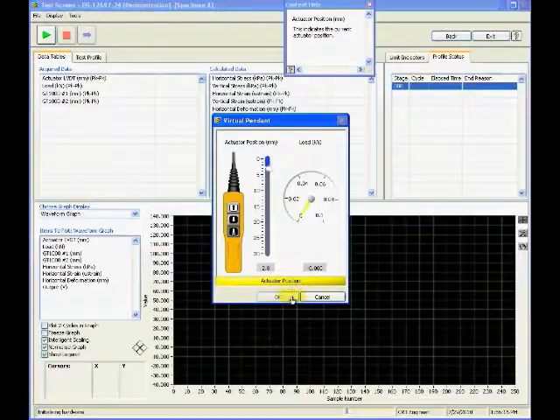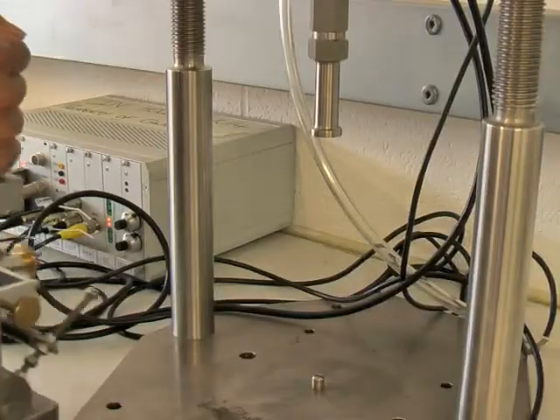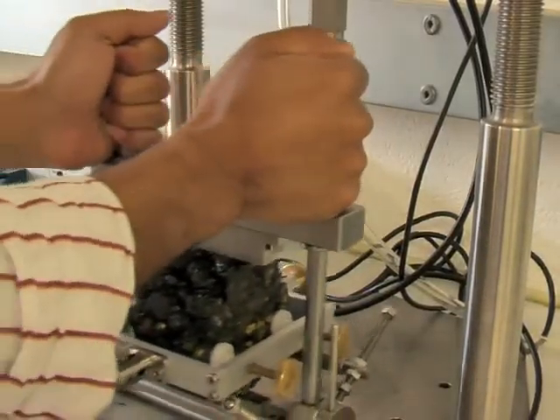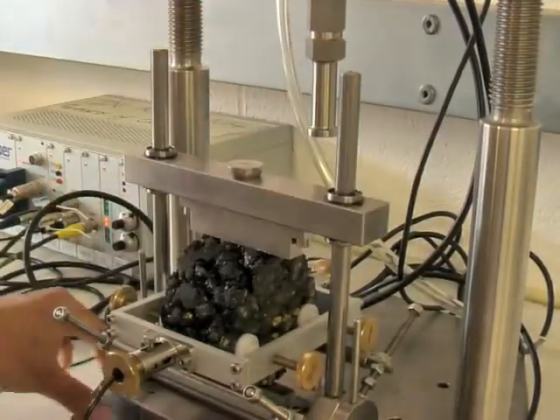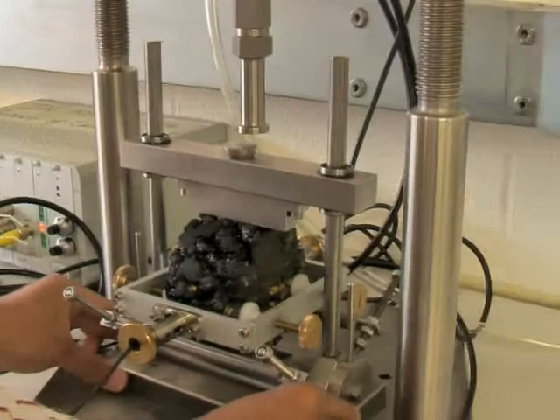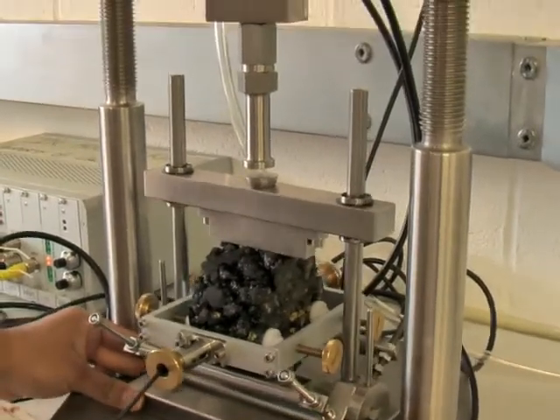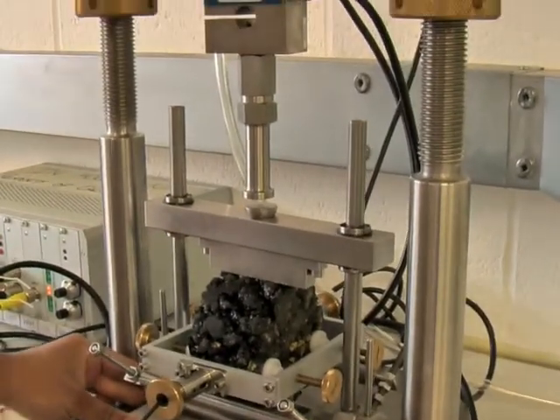The hardware initialization starts, so place the specimen under the actuator and send the actuator down to make contact. Press OK when the holding load is stable.